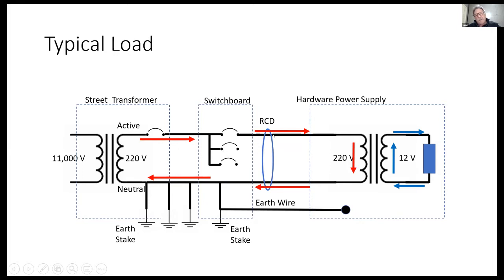And you'll see in the RCD, there's current flowing one way in the active and in the reverse in the neutral. The total magnetic field from that is zero, so the RCD doesn't see a fault. It's quite happy. And then in blue, I've got the current in the secondary of the power supply. And that's the important thing, the electrons flowing around that circuit are quite different to the ones on the primary. So that transformer is an isolated supply, and the two circuits are absolutely independent.